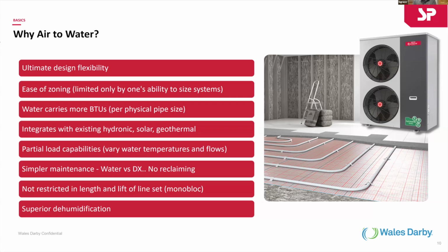And the issue with refrigerants is, if you oversize on the cooling side, the units don't work properly because you're not able to deliver enough air over the coil to help with the transfer of fluids and to keep the coil from freezing up. So it lends to the issues of dealing with refrigerants. Not to mention things like, did you pipe it right? Is it slanted properly? Because you've got to get the liquid back to the compressor so that it doesn't freeze up. And you're also dealing with very high pressures in very thin copper. So the lifetime of these units isn't very long because of what we're dealing with.